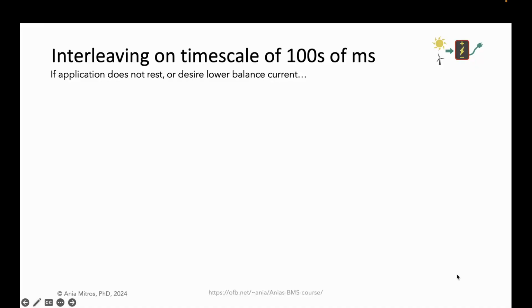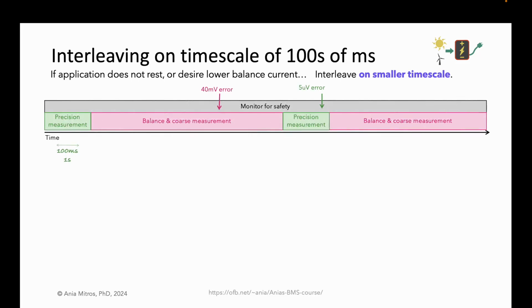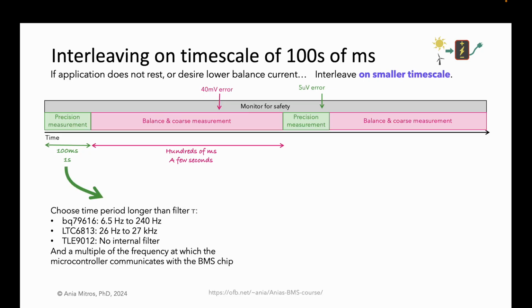Some applications don't have a regular rest period, or we wish to design for a lower balancing current. In those cases, we can interleave precision voltage measurements and balancing on a smaller time scale. We can monitor with high precision for 100 milliseconds or 1 second or some similar length of time, and then balance for a few hundred milliseconds or a few seconds with the consequently higher measurement error. For the precision measurement window, we should choose a duration longer than the time constant of the BMS chip's internal low-pass filter.